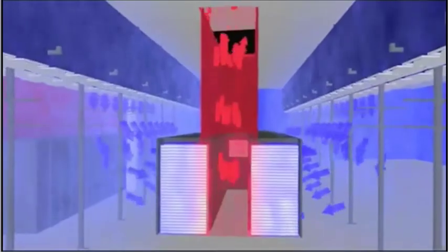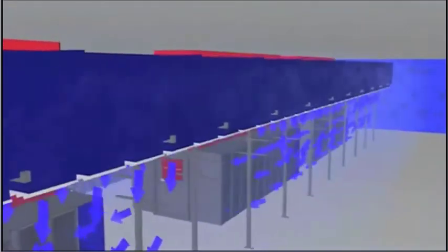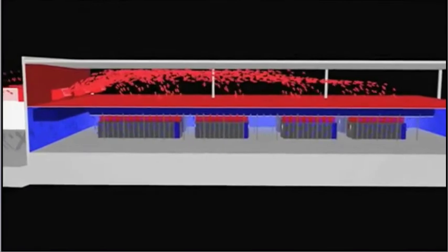What you're hearing in this room is the noise created by more than 1,000 racks jam-packed with servers, combined with the roar of the air being injected in here to keep them cool. If you walk into the room, you're in a basin of cool. The air gets pulled over by the fan units in the server racks, gets distributed through a hot aisle containment system and pulled back to a central location where it gets cooled down and recycled and pushed back out on the data center floor.